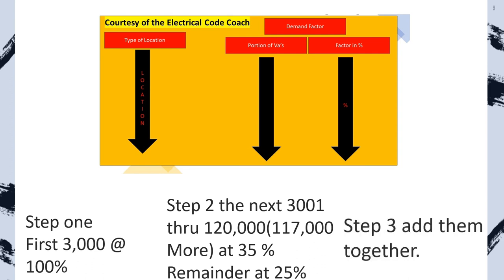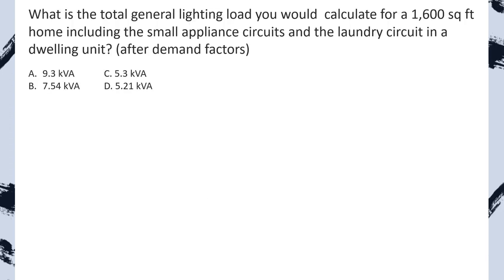Then step three, we add them back together. We take the original 3,000 that we set to the side, then we're going to take that new reduced load, add those two together, and that's going to give us our total load. Now: what is the total general lighting load you would calculate for a 1,600 square foot home, including the small appliance circuits and the laundry circuit in a dwelling unit after demand factors?